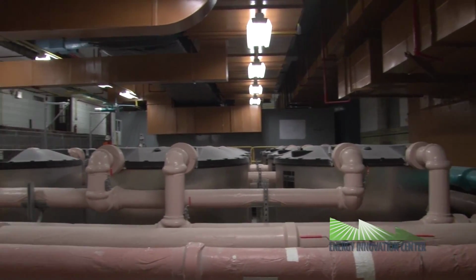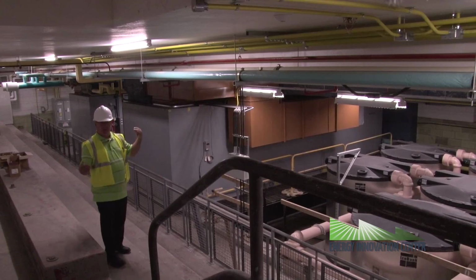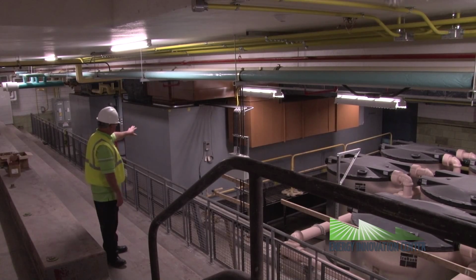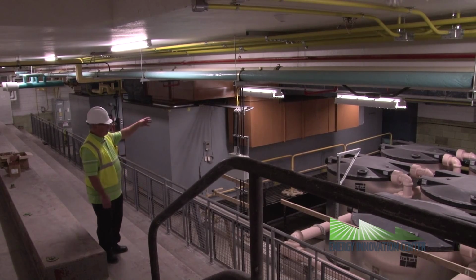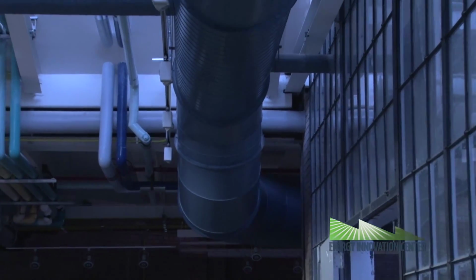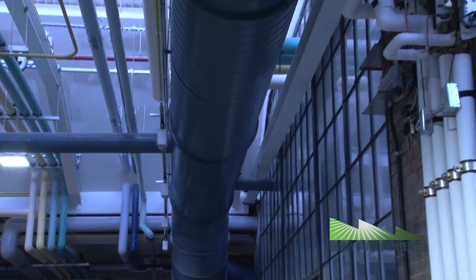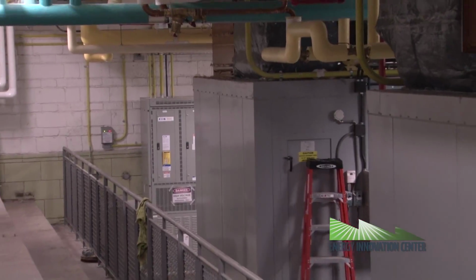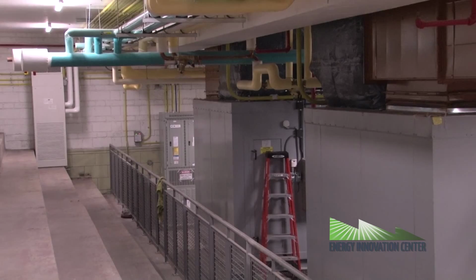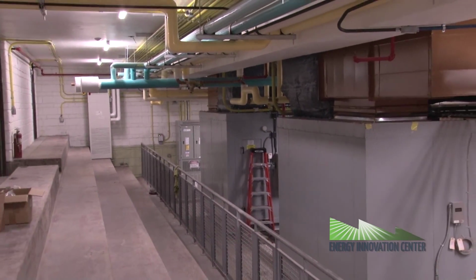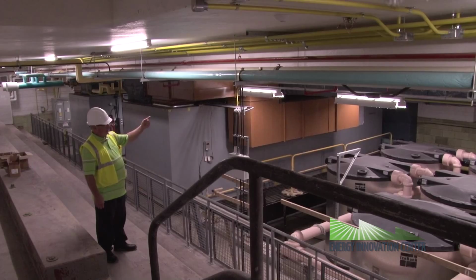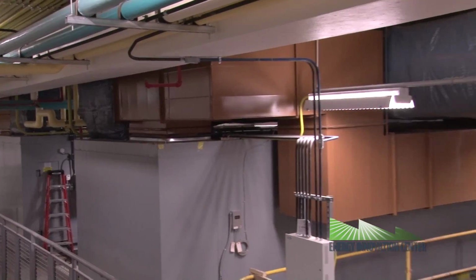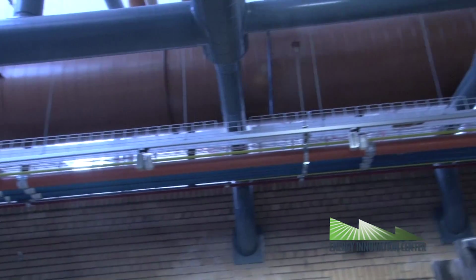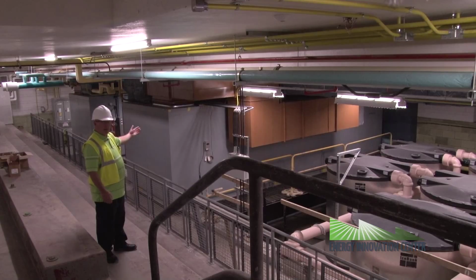This is the home of the dedicated outside air systems I've been talking about throughout the building. These two gray boxes bring in 100% outside air, whether the humidity is 90% or 40%, through high efficiency enthalpy and heat recovery wheels. It brings the air in and sends it to the building through the blue ducts. The brown ducting is exhaust air, so all the exhaust air brought back through the building goes through that, exchanging BTUs so we don't lose anything.